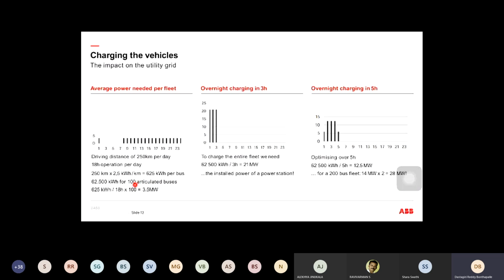If you have 100 buses, the total energy needed is divided by 18 hours, because we are not charging the bus when it is resting, we are charging it while operating. As long as the bus operates for 18 hours, that total energy is divided by 18 hours, and that's how you see a flat curve in the grid - just 3.5 megawatt flat over 18 hours duration.